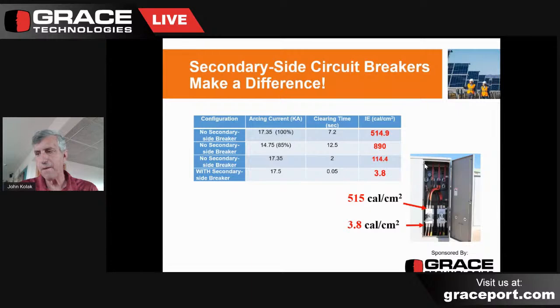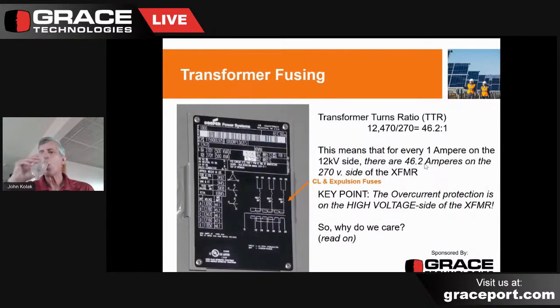Let's go to the next slide. Now, from an engineering standpoint, the transformer nameplate is very helpful. Here we see that this particular transformer is 12,470 volts on the high voltage winding, but only 270 volts on the low voltage windings. Now, if you take a look at it, you can see that they have the symbology there that shows you on the high side winding or the primary winding.